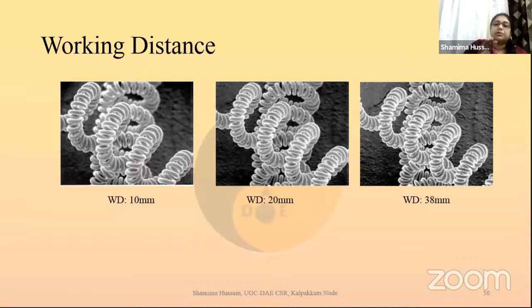When I increase the working distance to 20, please see this area, then you can make out better. Something extra, a spiral part, is visible here. That is, I've increased the view slightly. And when I put the sample stage even further down, to 38 mm, I can see a wider area. This is how working distance plays. Of course, it also plays with the focus, but I assume that whichever working distance we use, we are going to focus it properly and then get the image.